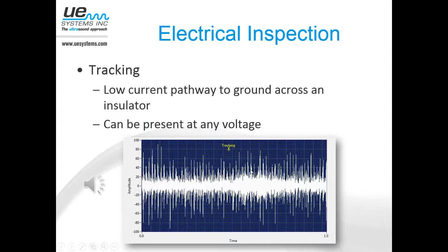The severe condition we detect is arcing. You can see a big amplitude change, going from soft to very loud to soft to loud, with a lot of individual events going on. In the case of arcing, as tracking gets more severe, these events last a lot longer, they're a lot wider. Earlier there were a lot of events, but they only lasted a split second, little pops and cracks. Once you get into a severe arcing condition where failure is actually occurring, you get very dramatic changes in amplitude, and the events last a longer time.